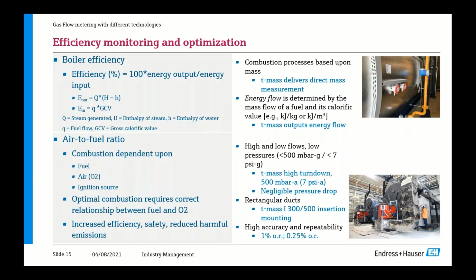Also, it comes in an inline and an insertion version. The insertion version is well suited for installations that may require rectangular ducts, but it can also be installed, of course, in circular pipes. Here we see in the picture on the right a combustion air application where the T-mass is inserted in a rectangular duct. The high performance of T-mass is also well suited for use in boiler efficiency calculations. Next slide, please.